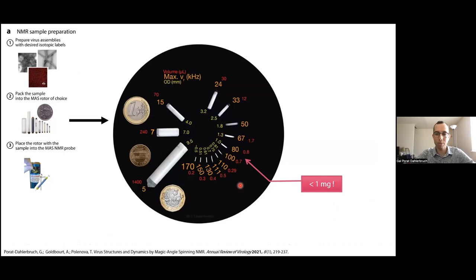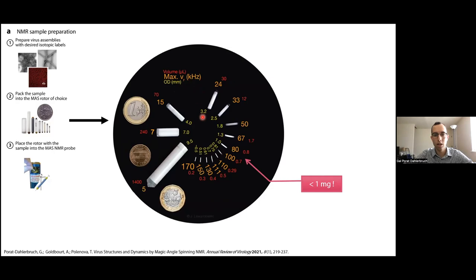Now that we understand the principle of MAS NMR spectroscopy, I want to review the process of protein structure determination by magic angle spinning NMR. The sample is prepared, isotopically labeled, and packed into an MAS rotor. MAS rotors vary in sizes, which determine the available sample volume and maximal MAS frequencies. For example, the 3.2 millimeter rotor can spin at up to 24 kilohertz, so we would mostly do carbon-detected experiments, and the sample volume is about 30 microliters.